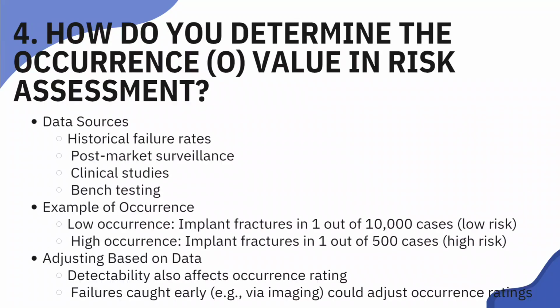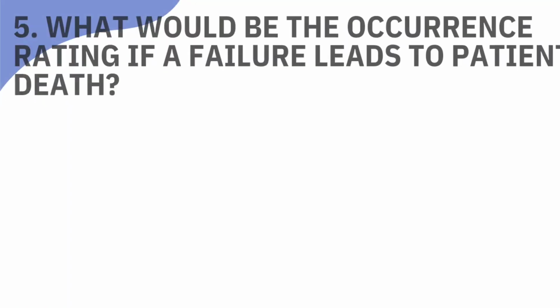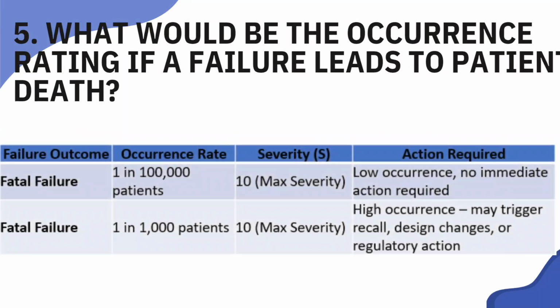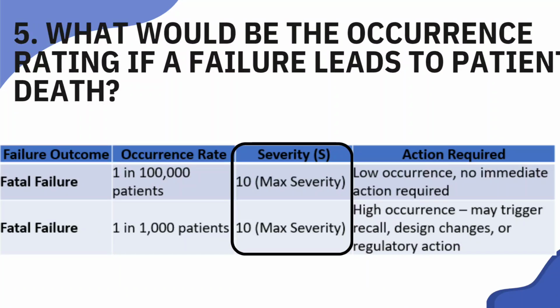I appreciate that you emphasize data-driven decision-making. Using historical failure rates, post-market data, and clinical evidence is critical for accurate risk assessment. 5. What would be the occurrence rating if a failure leads to patient death? Okay, so severity S for death is always maxed out, typically 10 on an FMEA scale.